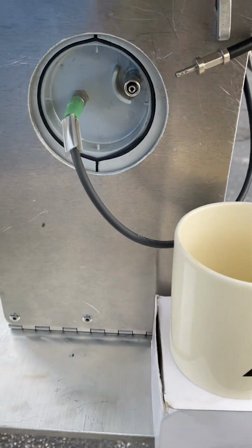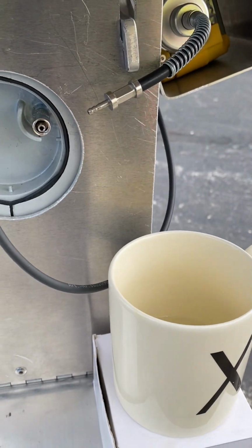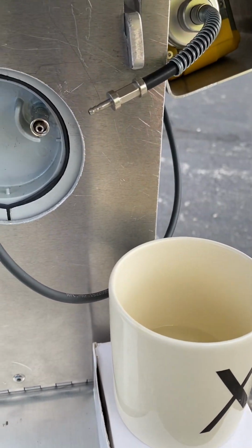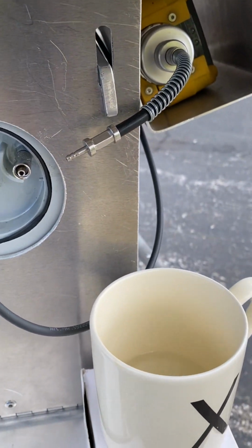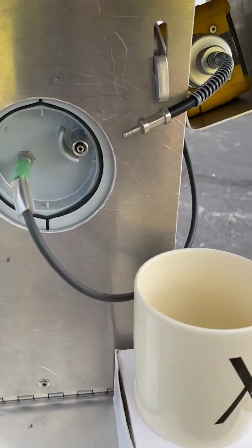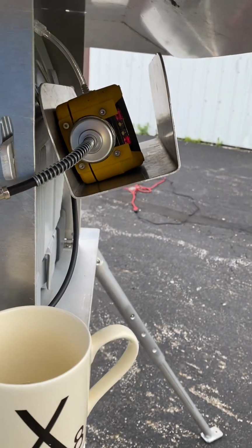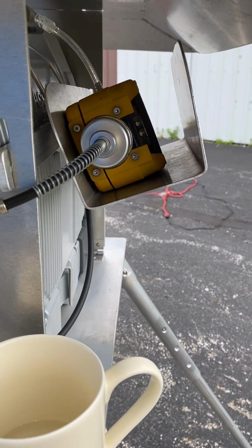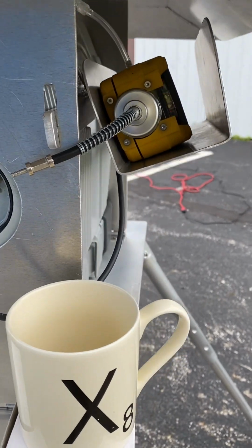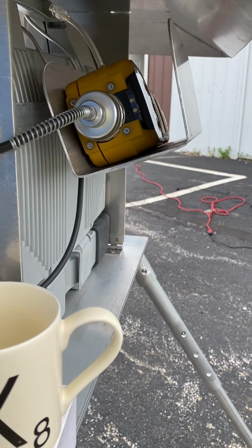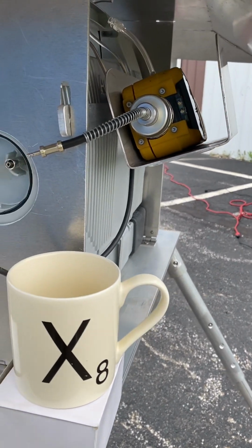Now the wind is blowing and it's creating a little bit of an air current in here. So we're getting that little plume and a little bit of acetone every so often. But that is the interface. Now, again, I have it connected up to a MiniRAE 3000, but you could use any third-party device of your choosing, as long as we can interface with it and work with it. So that's something to consider. We have a couple of other different devices, IMS detectors, but I can see a particulate monitor as well being connected on this if you wanted that as well.